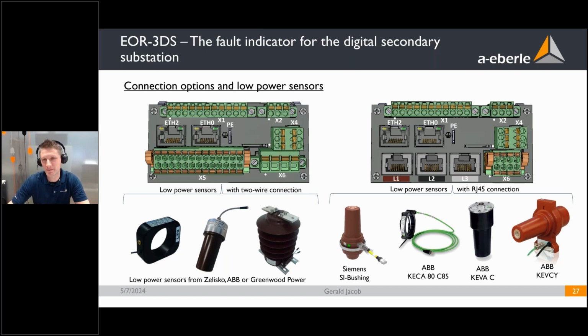Okay, and then let's come to the right part of this page. Second option of sensors that can be connected to the device, and these sensors are with RJ45 connector. As you can see, for example, Siemens SI bushing that comes with such a RJ45 connector, or different sensors from ABB. The Siemens SI bushing and the ABB KEVCY are bushings that are installed in the compact switchgear directly, and inside these bushings the low power sensors, voltage and current, are already installed, and out of this bushing comes an RJ45 that can be directly connected to one of the 3 phases of the EOR-3DS.